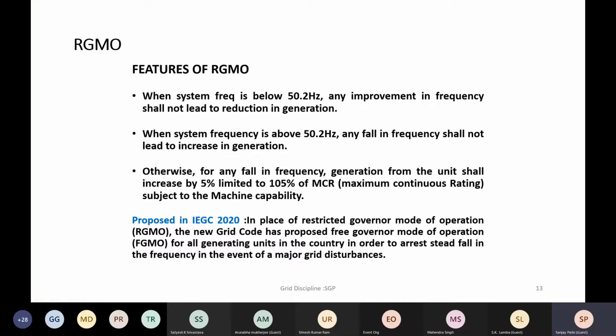So RGMO as such was a provision because the free governing mode of operation had not been successful. People were keeping the deadband under FGMO so wide that virtually FGMO was not really getting implemented, because, as you said, the commercial mechanisms were actually proving to be counterproductive in free governing mode of operation. With AGC now, the same should not happen, and I'm sure the provision should happen.